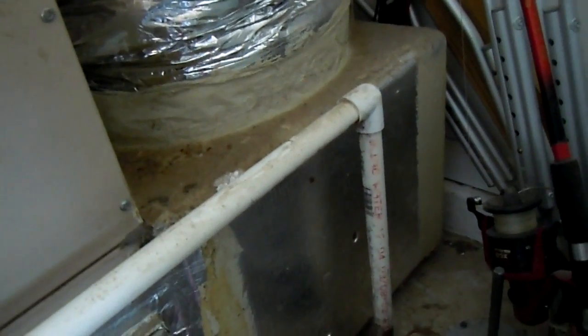Now right here on this side I made another hole. It didn't really work out very well. I had a 90 up in the ceiling in the attic there that was interfering with getting an accurate reading, so I decided to come down here, right here where I'm less liable to get much interference from any kind of 90s or anything, and I was able to get an accurate reading that way even though the air has to turn here and then go up into the air handler.